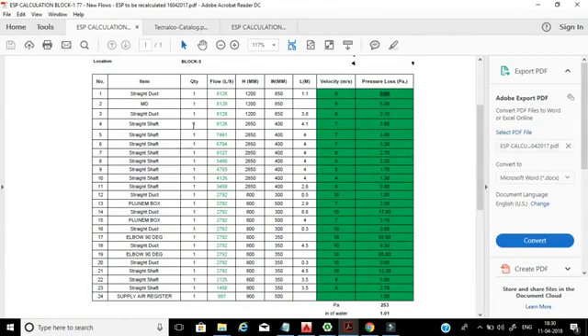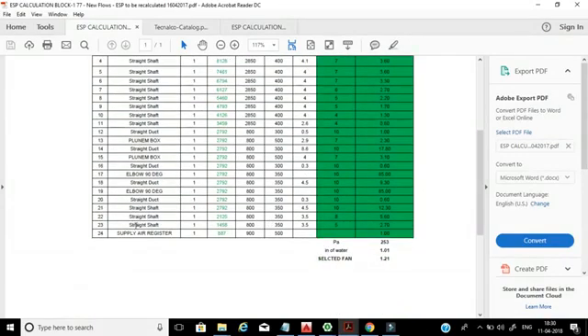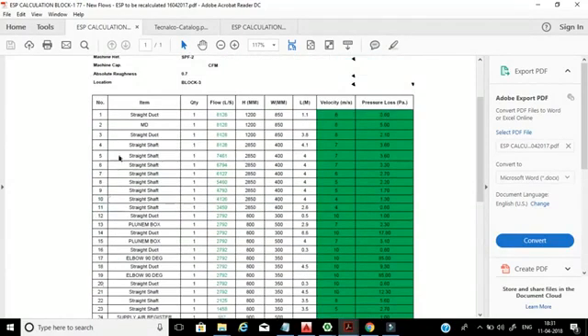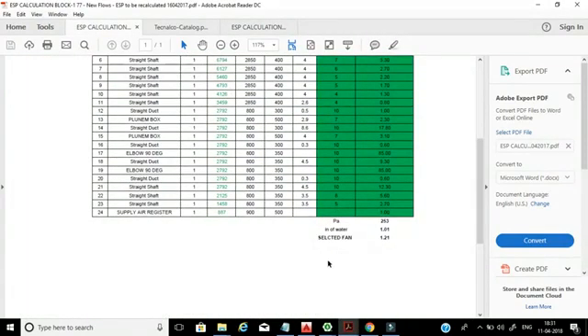In this ESP calculation you need to mention all items: straight duct, motorized dampers, plenum boxes, elbows, supply registers, grilles or diffusers, flexible duct — everything. This is for one unit, one FCU or fan coil unit. In the summary, we mention the total Pascal for that machine, then convert to inches of water. The conversion is Pascal divided by 250, which is a constant value, to get inches of water.